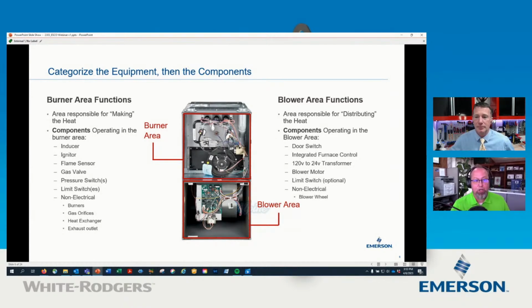Exactly. But the first thing you're actually going to be able to notice is the inducer motor starting. It's going to be something you can see and hear. It doesn't matter if it's a single-stage or a two-stage inducer motor. When it's time for it to come on, you're going to be able to see and hear it come on. If you don't, you know that's where you start. Your first step is that you've caught it with your senses.